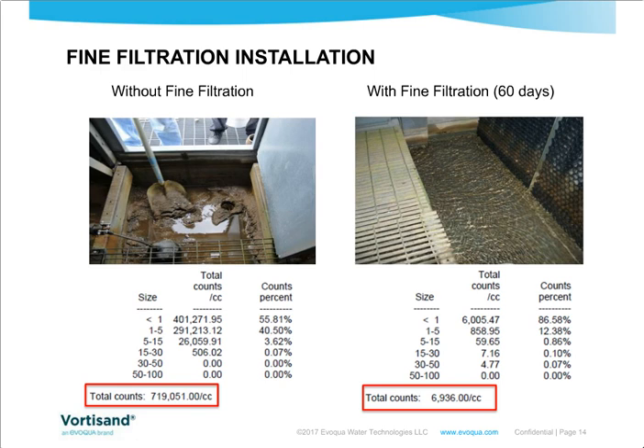Now, this is an example. You have two images here on your screen. The left image shows a cooling tower that was operated with a filtration device called a centrifugal separator. So that's without fine filtration. This is an extreme example, but that cooling tower was operating at very high TSS levels. And once fine filtration was installed, after 60 days of operation, you can see a dramatic improvement in the water clarity here, which is one definite aspect of understanding the improvement of your filter technology.